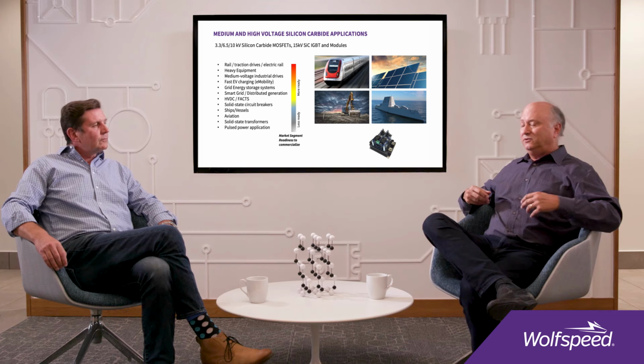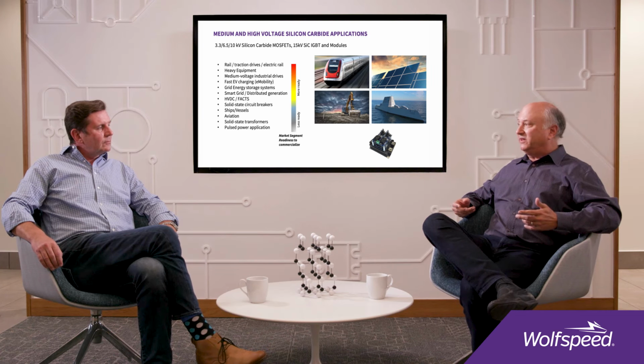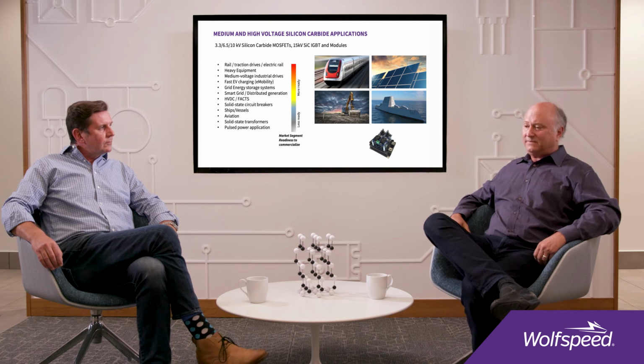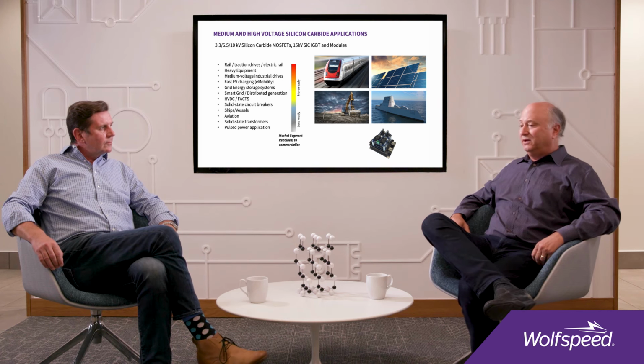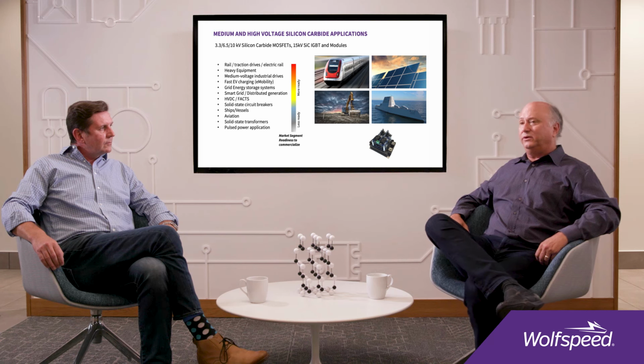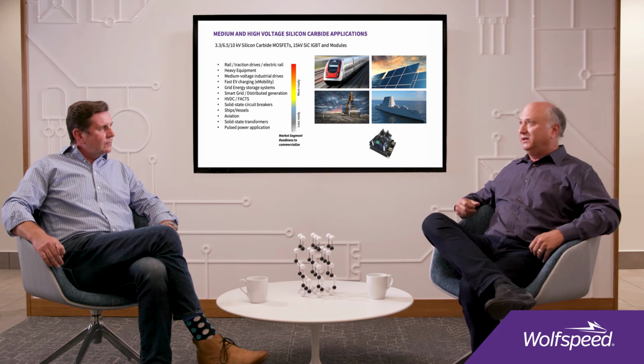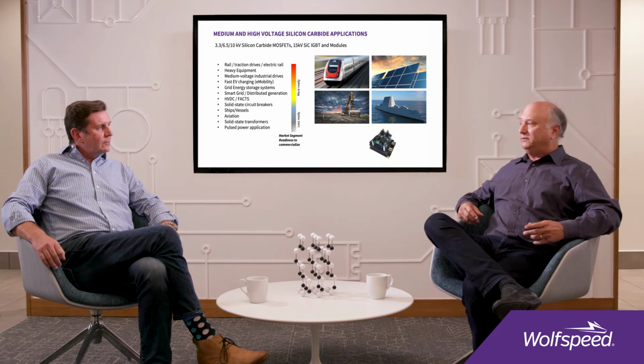Typically you can do a grid tied inverter with a solid state transformer, and we've done a number of system demos. We did one funded by the Department of Energy for a 250 kilowatt grid tied inverter, trying to tie to 13.8 kilovolts on the grid side - 13.8 being a typical localized grid. We did that with power modules using 10 kilovolt silicon carbide MOSFETs.